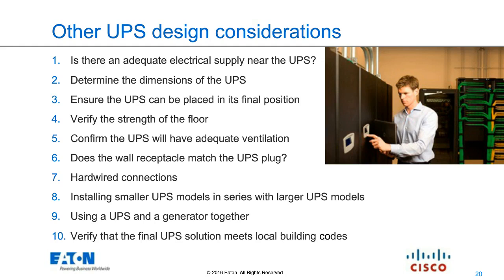When you start to get into larger systems, plugs and receptacles, at least from the UPS interface, is kind of irrelevant because you're looking at hardwired connections. In the U.S., 30 amp is the rough upper limit on what you can bring into a UPS through a plug. There are some considerations that will get you up to 60 amps, but we don't see a lot of that in the U.S. It's more of a Europe connector. So hardwired connections, well, there are considerations that must be made there as well, and that's almost always going to require an electrician. So it's good to think about up front.